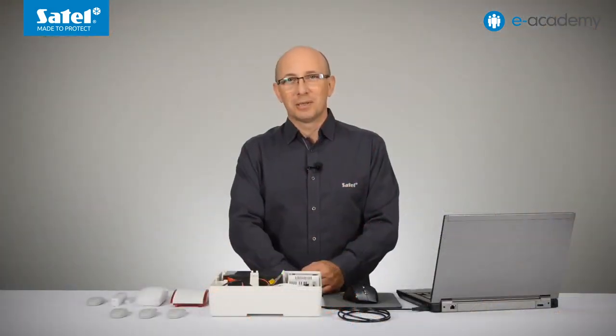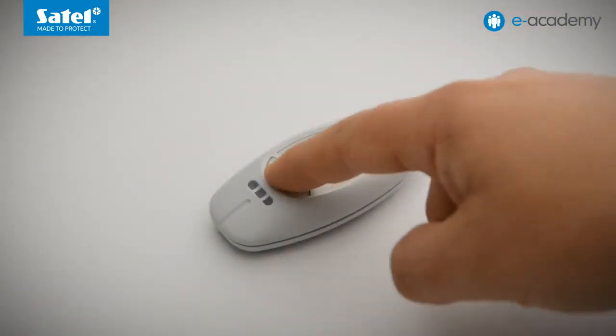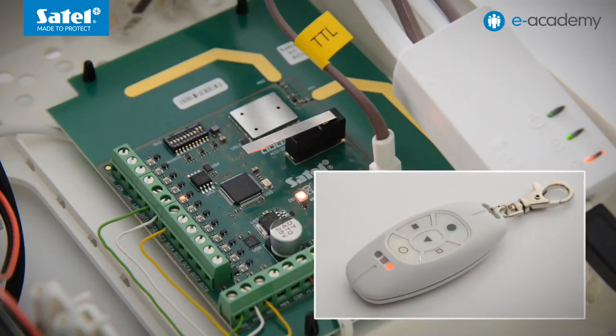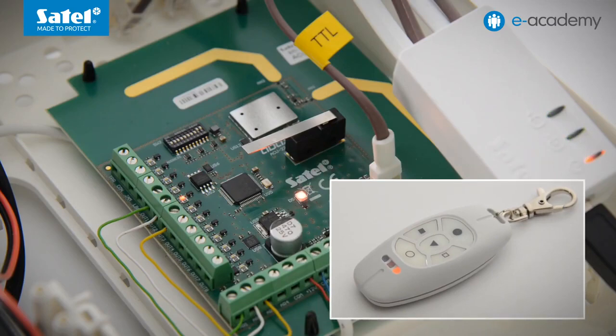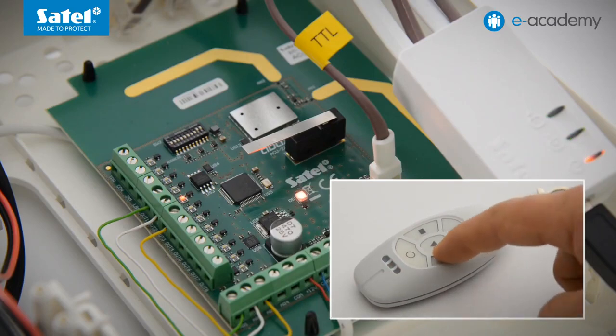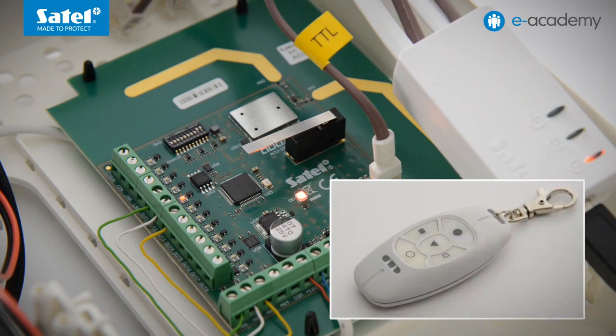Let's check how it works. I press the empty circle button. The out 1 output has been activated. A red LED has signaled the violation of the AR1 input. Now I will use the empty square button. The out 2 output has been shorted to ground for 5 seconds, hence the AR2 input will also be violated for such time. The red and orange LEDs have confirmed violation of the AR1 and AR2 inputs.